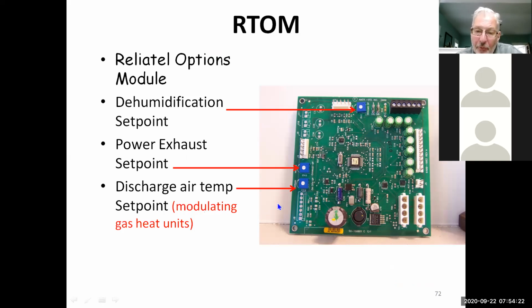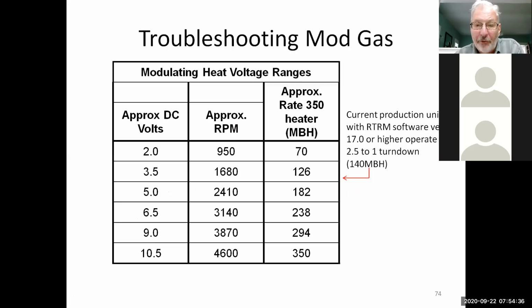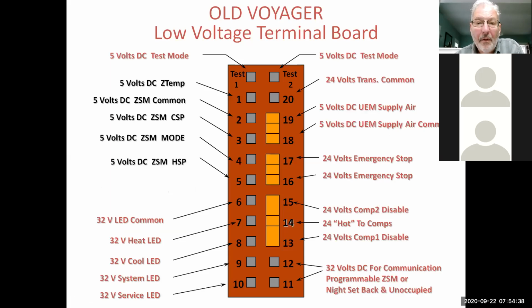The modulating unit actually works with a discharge air sensor, and it modulates the blower or the burner up and down based on that temperature sensor, and then your set point is right here on the board. So again, modulating is a little different animal. If you run into them and you got questions, give me a call. And that's about all I'm going to spend with them.